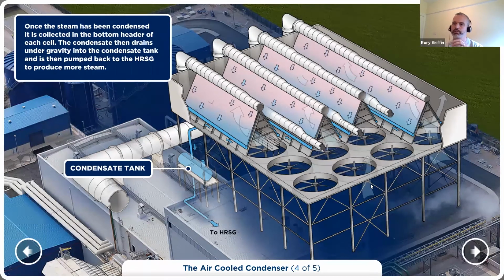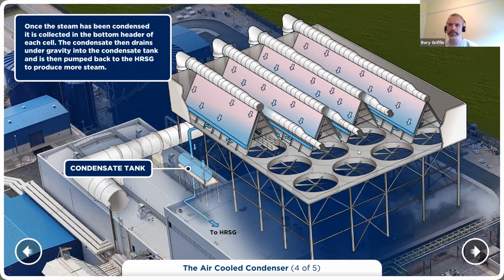I suppose one thing to bear in mind is when the machine is at lower output, not all the fans need to be in service, and as the machine picks up, you should have at least 19, maybe 20 fans in place. But in the winter months, even if the plant's at a higher output, ambient conditions are good for the cooling. So it's probably the summer months, if all the fans are available, you'll typically have a lot of them running when the plant's up at a decent output.